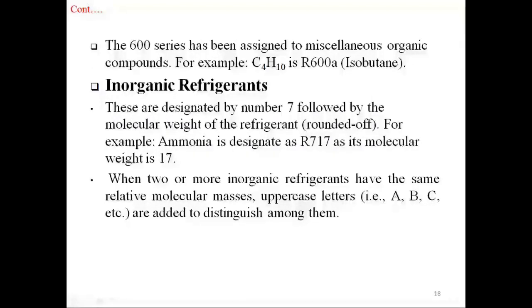The 600 series has been assigned to miscellaneous organic compounds, for example butane and isobutane. The formula of butane is C₄H₁₀ and the formula of isobutane is also C₄H₁₀, but both are isomers, so isobutane is known as R600a. Inorganic refrigerants are designated by the number 7 followed by the molecular weight of the refrigerant rounded off. For example, ammonia is designated as R717, as its molecular weight is 17.